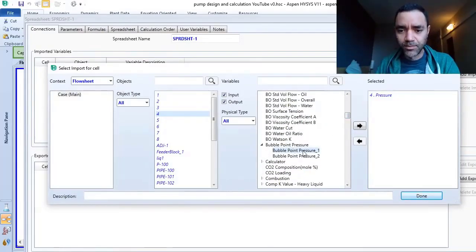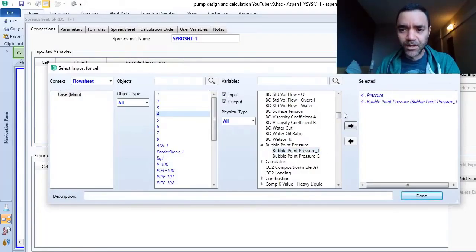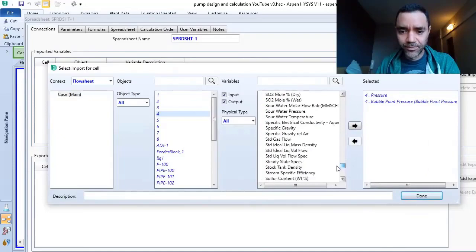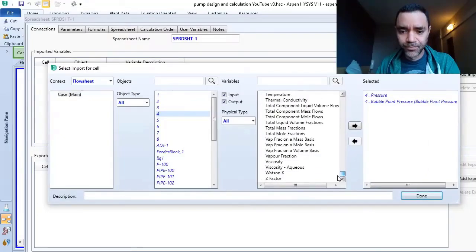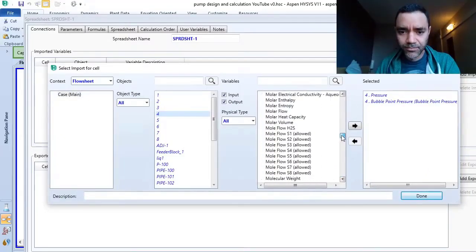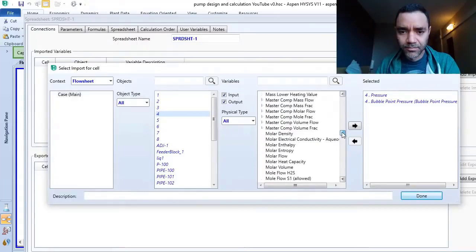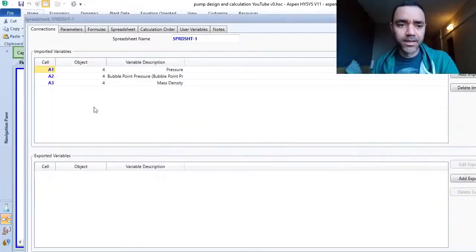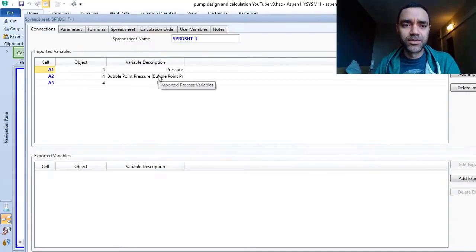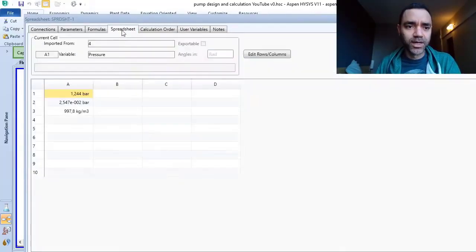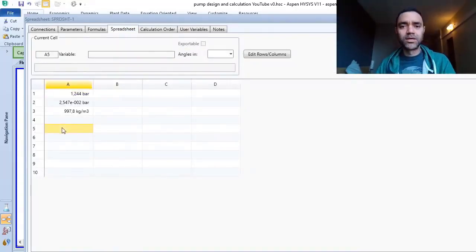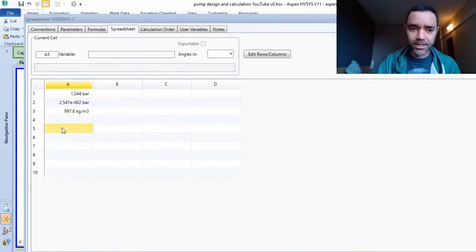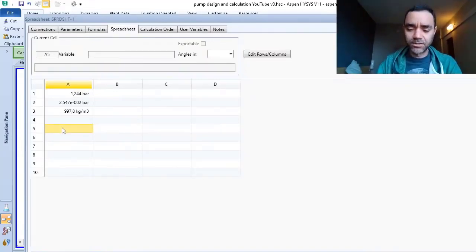I will use the bubble point pressure 1, and I need also the mass density. Okay, I have the three variables that I need to do the calculation and I have the identification cells. I go to spreadsheet, and now I will do the calculation of the NPSH available considering only this information and not the velocity.